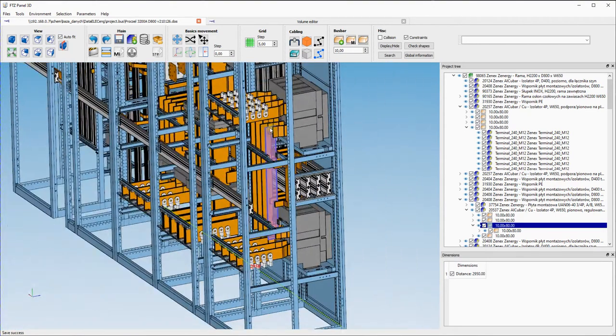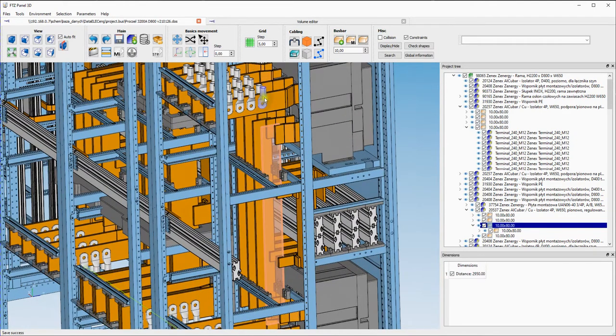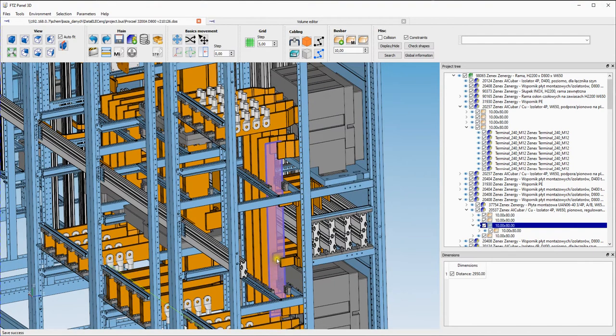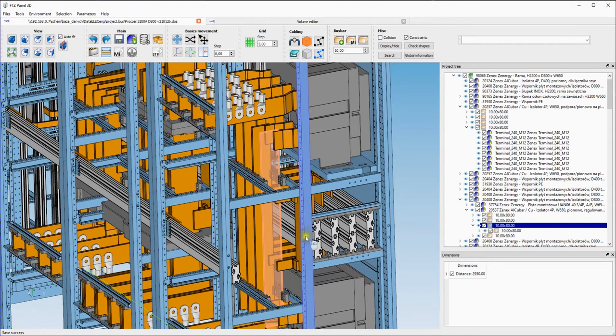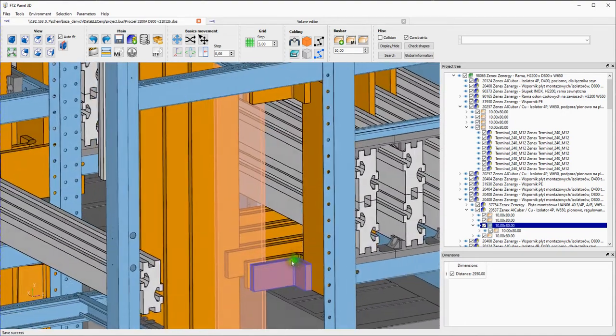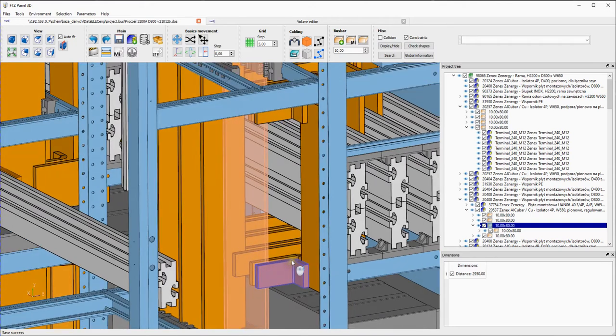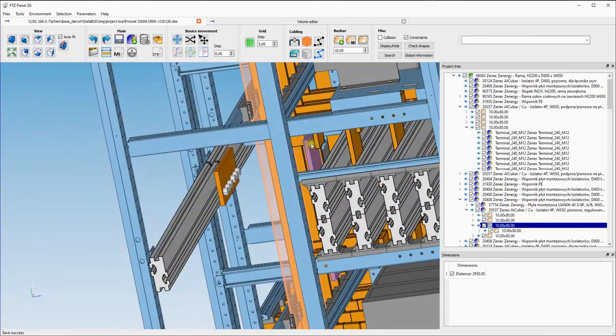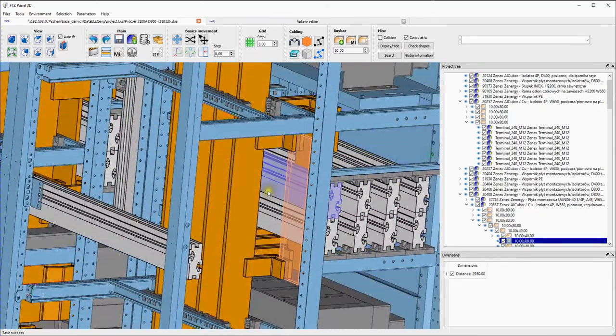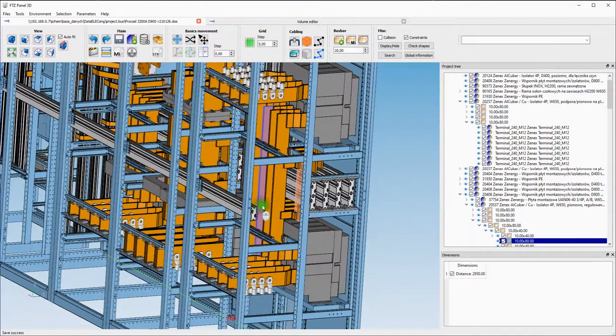Yeah. This bus bar is 80 by 10, so one bus bar 80 by 10 can manage 1600 and the second 1600. Here the small bus bars are 40 by 10, but there are 4: 1, 2, 3, 4. So it's the equivalent of 80 by 10, but one from the top, the second from the bottom. And it goes to 180 by 10 outgoing.